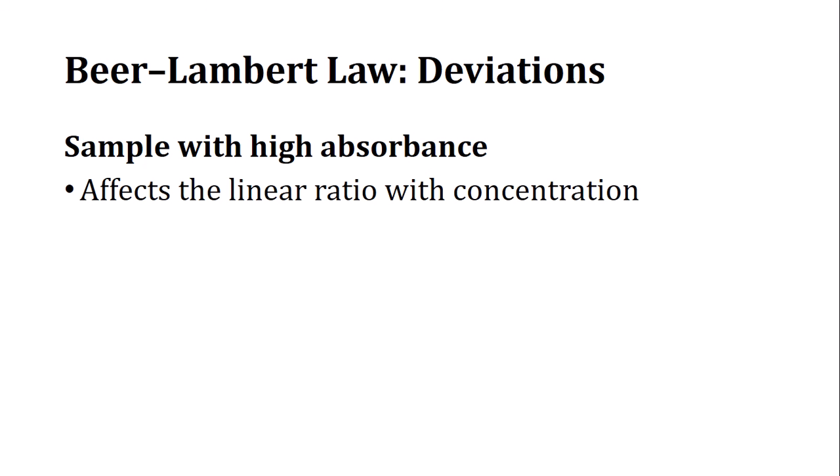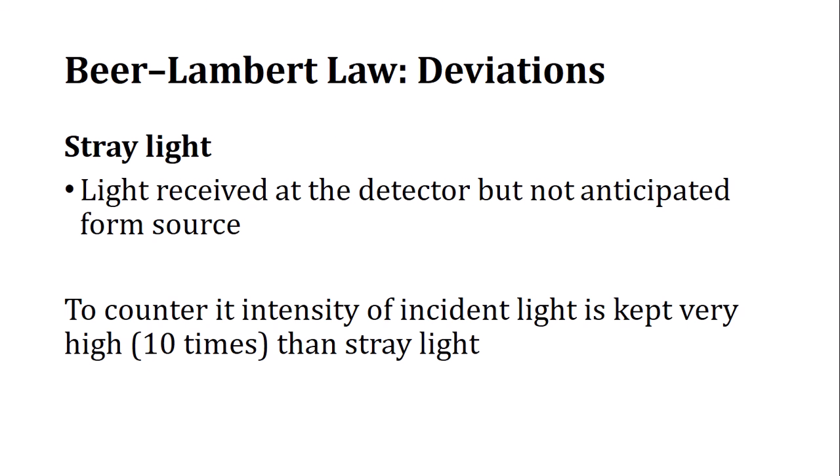Another problem is stray light. If any instrument has some extra stray light, that stray light may reach the detector and affect the actual reading. To address this, we concentrate on light coming only from the source and increase the intensity of the source light so that the effect of stray light is minimized.